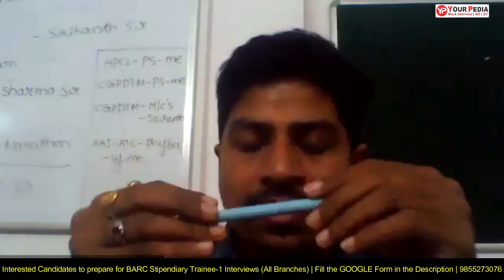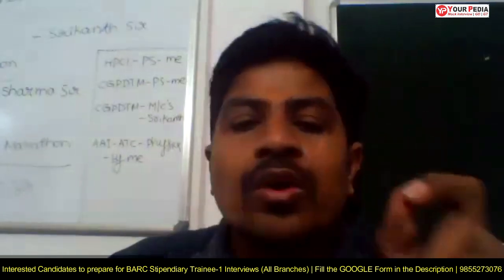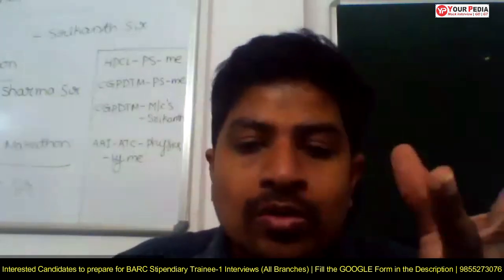What is corona? If you take a power conductor, a transmission line conductor, the air surrounding the conductor is getting ionized because of electric field intensity. If the electric field intensity is more than 21.1 kV per centimeter RMS value or 30 kV per centimeter peak value, then the air surrounding the conductor is going to get ionized and act like a conductor. Due to the process of ionization, some power loss is going to happen. During this ionization process, you're going to hear some sound, some ozone gas is produced and some light is also produced.